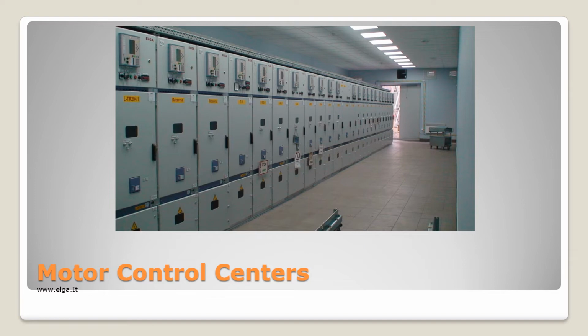The motor control center gives us a way to stop and start the motor, and to do so while we have additional protections that are more advanced than the simple system of using a switch that you might use to turn on a light bulb, as an example. Motor control centers provide a way to distribute power, to do so safely, and to provide additional protections for the motor loads that are connected to the system.